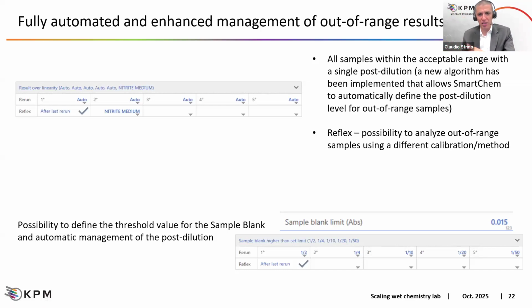Moreover, we can also monitor the blank of our samples. We already saw in the previous slide that we can manage true sample blanking in the cuvette. And we can determine the threshold value for the sample blank, and if the blank of our sample exceeds the value set for each method, we can also define post-dilutions to dilute the sample, consequently diluting the color of the sample itself. One typical case for customers applying this is when they need to run, for example, pollution testing on soil extracts, or manage wastewaters, where those matrices could sometimes be very, very dark, and the color of the sample itself can affect the colorimetric determination. This is why we implemented this feature in our software platform.